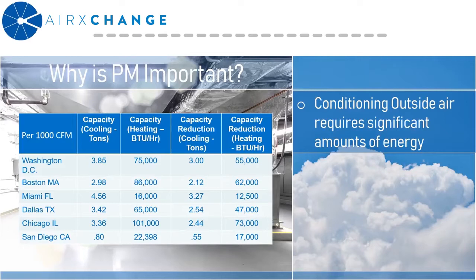On average, an energy recovery device is about 4 to 6 times more efficient at conditioning outside air than your typical primary heating and cooling element. So even small amounts of performance degradation could have a substantial impact on the way the building operates.